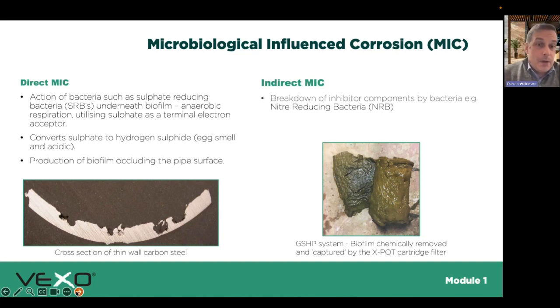So the bacteria itself will create a biofilm eventually. This slimy looking goo, which you can see in the picture on the right hand side, that's actually a cartridge filter under there, and it's literally the layer of this slime that has peeled off. This was a US military base in upstate New York. They were using a ground source heat pump system and having all kinds of problems. And the other thing is they produce acids, and you get smells as well. You typically know on a cooling system in particular, you get this horrible smell.